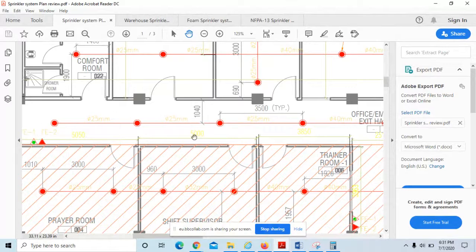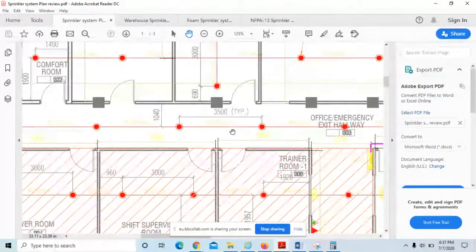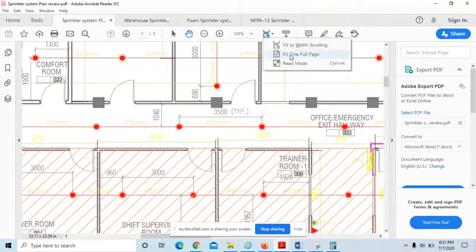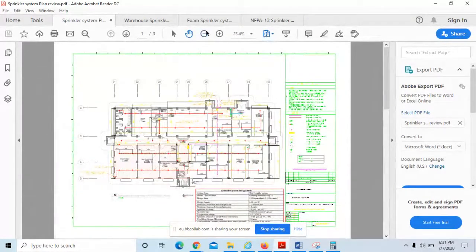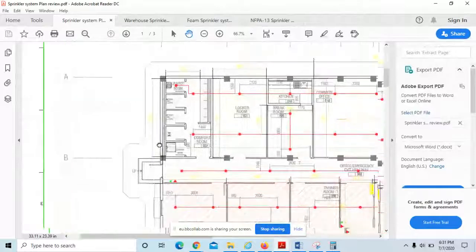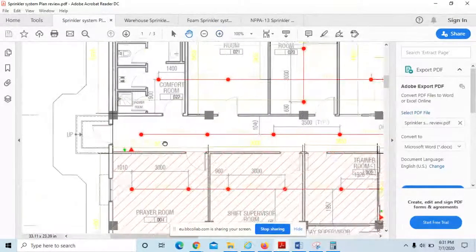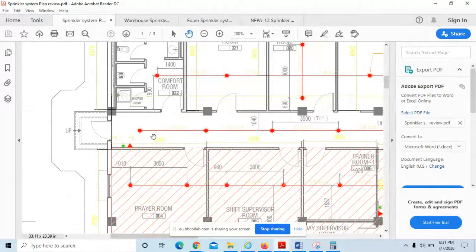There is no location for the hangers, and you never know what is the maximum distance they are going to follow. They must put a symbol of the hangers on the pipe only. Something like the diagonal line should be there, because without those hangers we cannot make sure what is the distance between two hangers, and what is the distance without hanger for the last stage sprinklers.